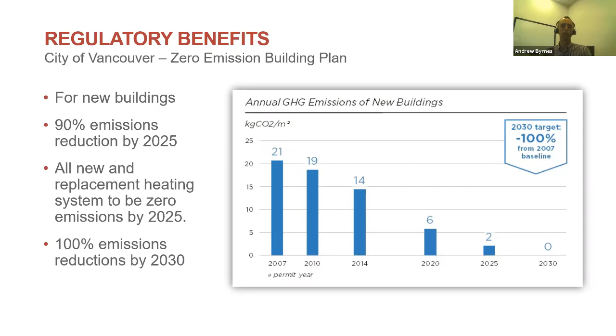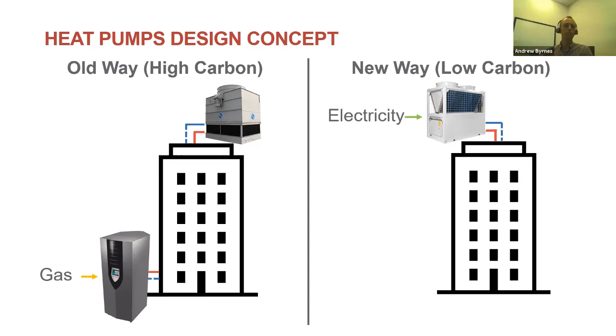Fortunately, it's not really that much of a pivot to use a heat pump for heating a building compared to the old way of doing things, using a gas boiler and chiller or cooling tower configuration. On the left is a building that uses a gas boiler in the basement and a cooling tower on the roof, with gas as the fuel going in. It's not substantially different to heat and cool the same building with a heat pump, shown on the right. Maybe a rooftop mounted air source heat pump that pulls heat out of the air in winter and provides heating into the building's hydronic system, then runs in reverse in summer, providing chilled water and sending heat out into the air, much the same way a cooling tower would. So a heat pump can be substituted for a gas boiler very effectively in many cases.